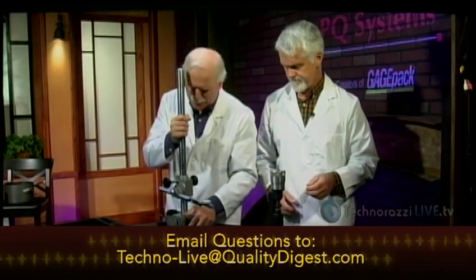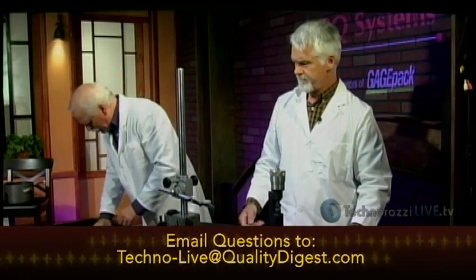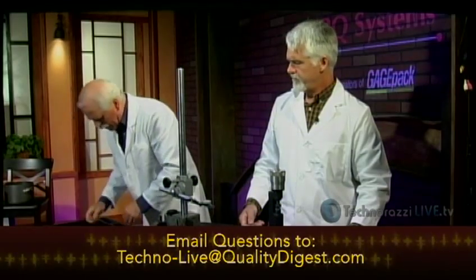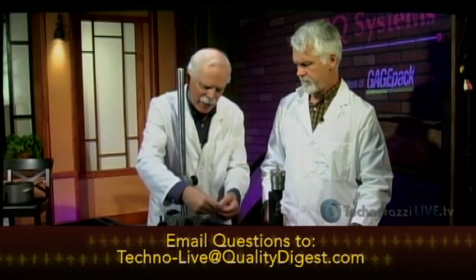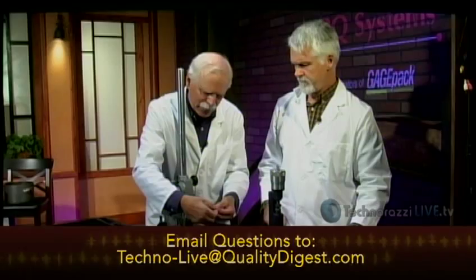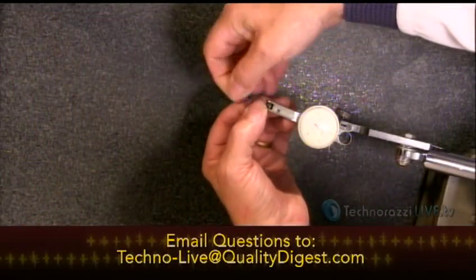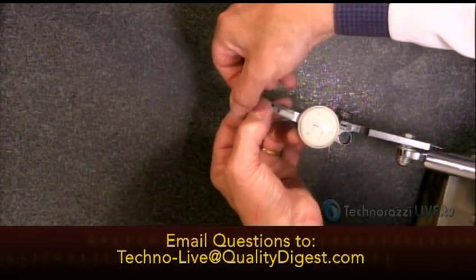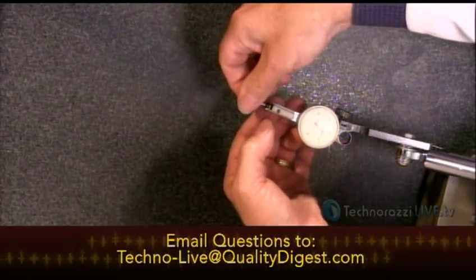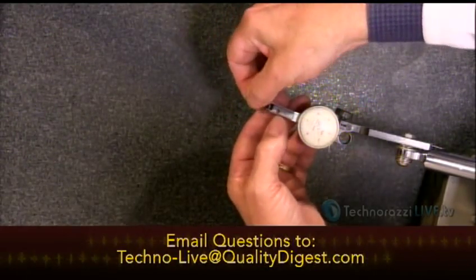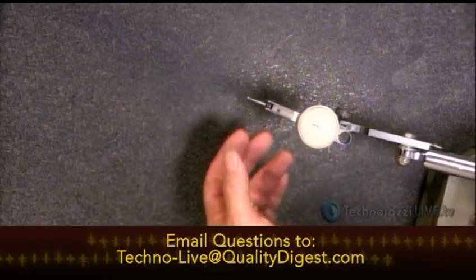We're going to set up, even though normally for flatness measurement you'd use a higher resolution indicator than what we have. This is a 5/10,000ths of an inch, or 5/10. Usually you would use a 1/10. In our lab we use one that goes to 5 millionths, but that's irrelevant. Let's start out with what we have.